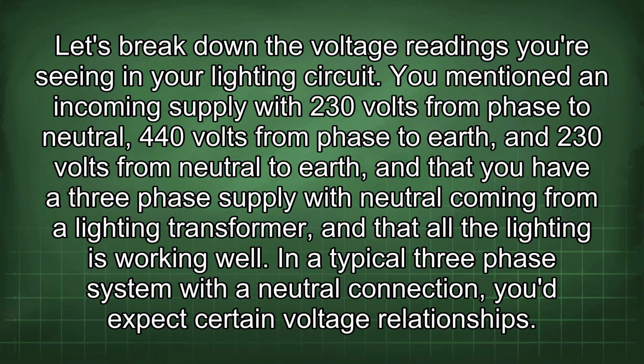Let's break down the voltage readings you're seeing in your lighting circuit. You mentioned an incoming supply with 230 volts from phase to neutral, 440 volts from phase to earth, and 230 volts from neutral to earth, and that you have a three-phase supply with neutral coming from a lighting transformer, and that all the lighting is working well.